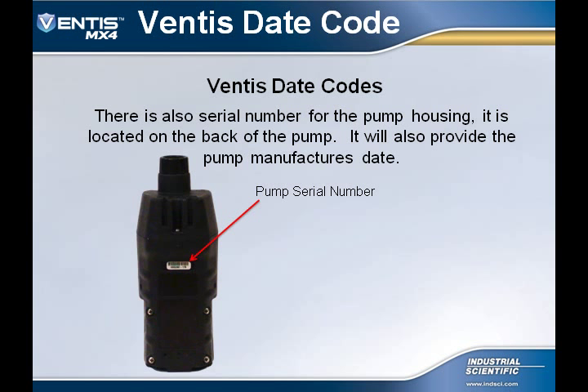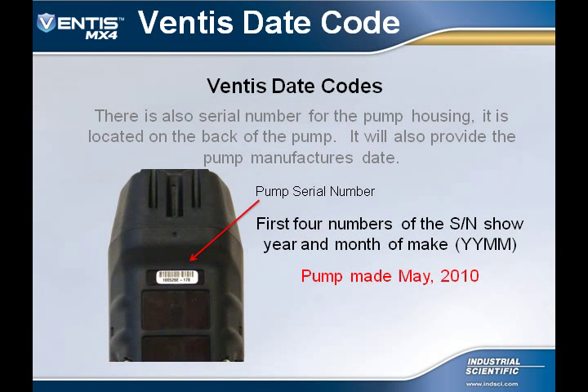The Ventis MX4's pump also has a serial number and is located on the back of the pump assembly. The date code for the pump can be determined by looking at the first 4 numbers of the serial number. The first 2 numbers are the year in which it was made, and the second 2 numbers are the month in which it was made. As you can see, this pump was made in May 2010.